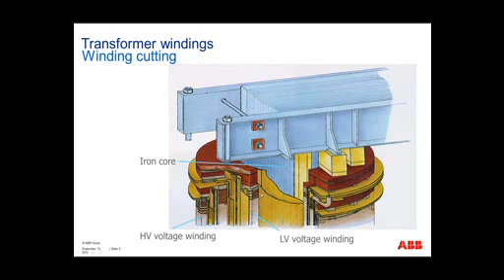Closest to the core, you'll have your low side voltage winding. This low side voltage winding is separated by insulation. And you can see that if this insulation breaks down, you'll actually have a phase to ground fault inside the transformer, to the core. So insulation breaking down could be a cause of a fault on the low side of the windings. Also, between these windings, you'll have insulation too. That is a possible cause for faults inside the transformer. This insulation could break down and cause a fault inside the transformer.